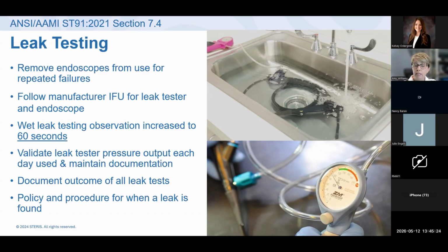And documenting the outcome of the leak test. So clipboard, tracking system, 3-ring binder, whatever works for your facility, but your staff should be checking those testers and saying, yes, valid, works, pressure output, whatever you decide, however you want that to look. But you should have a record of that and you should be able to produce it if requested in a survey. All right.